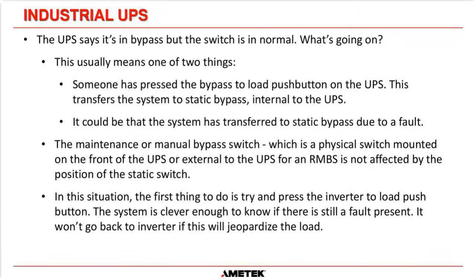If the UPS says it's in bypass, but the manual switch is in normal, what's going on? Well, that's usually one of two things. Either A, someone has pressed the bypass to load push button on the UPS, which has transferred the system to static bypass. Nothing to do with the maintenance bypass switch. Remember, that's a rotary handle. It's just a push button to transfer the system to static bypass. Or it could be that you had an overload on the output of the system and it transferred to static bypass automatically.